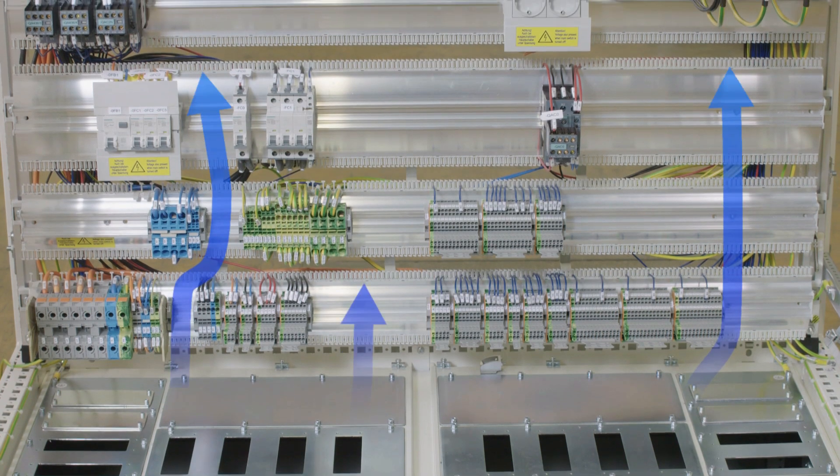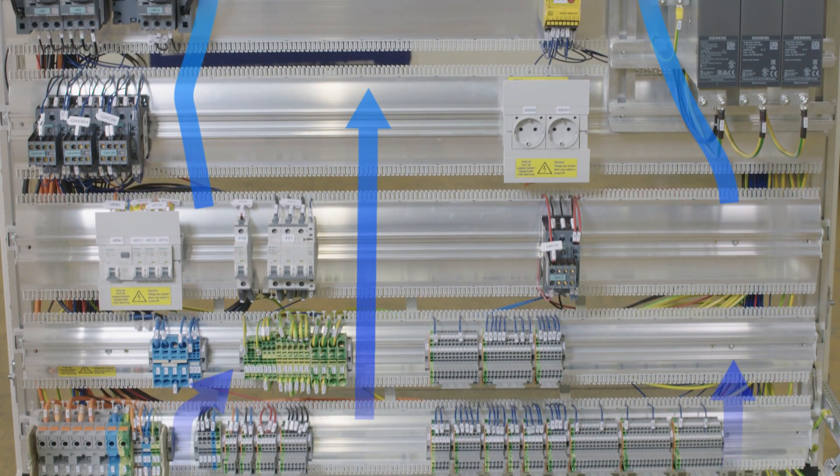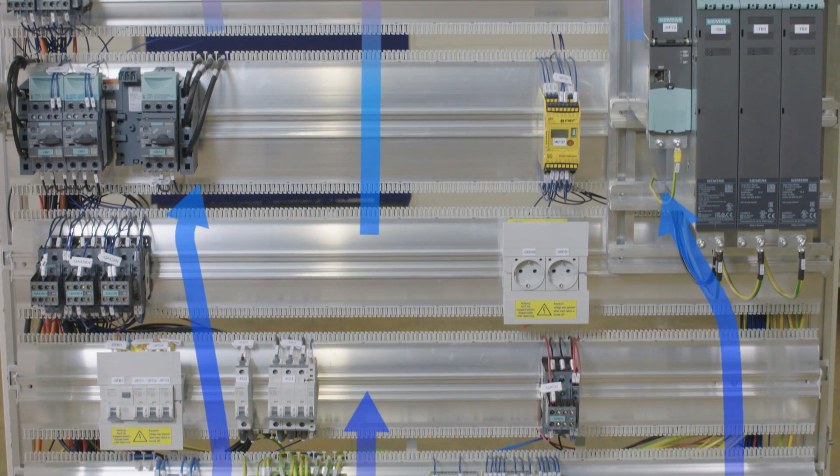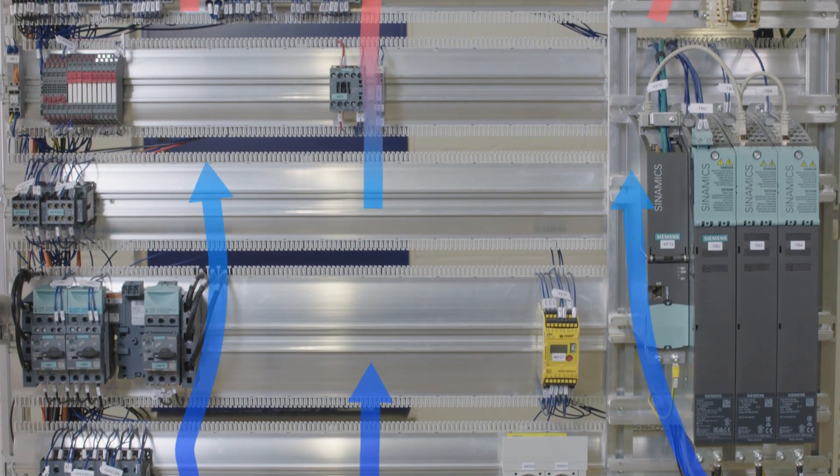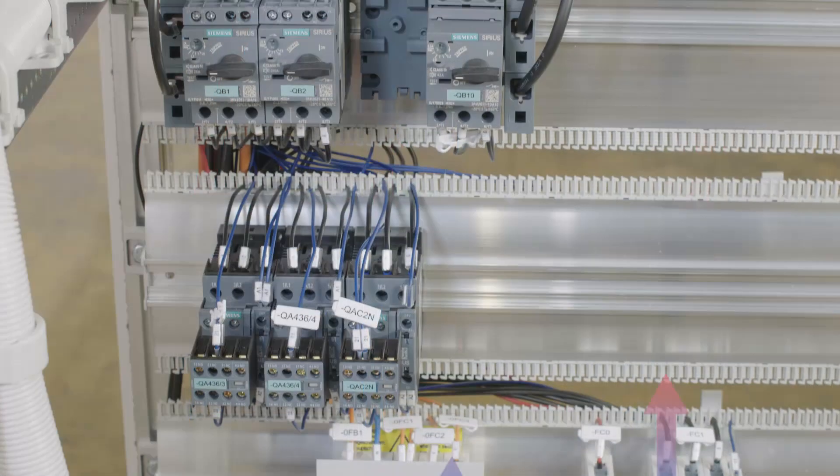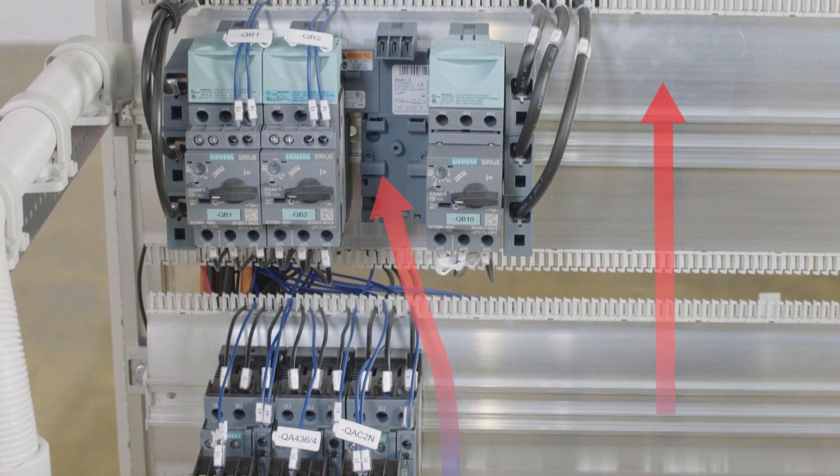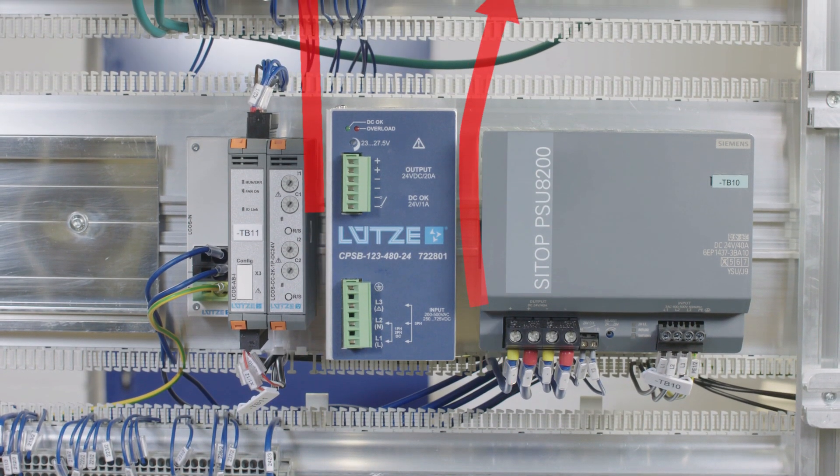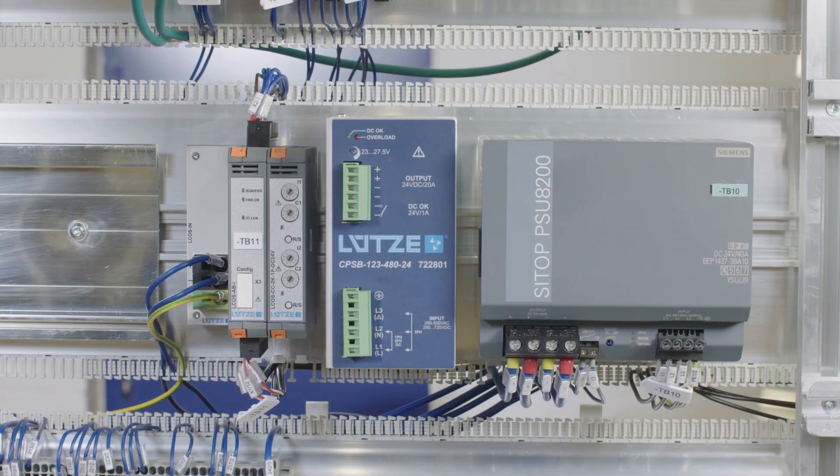Due to the division into an assembly and a wiring level, air flows past the modules and wires almost unobstructed. As a result, waste heat is quickly dispersed to the exterior panels of the cabinet. The resulting homogeneous interior climate ensures a longer component life and thus reduces the risk of machine failures.